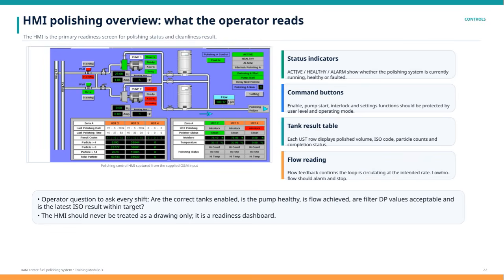Next, the command buttons available, such as Enable, Pump Start, Interlock, and Settings, are protected by user level and operating mode to ensure only authorized personnel can make critical changes.